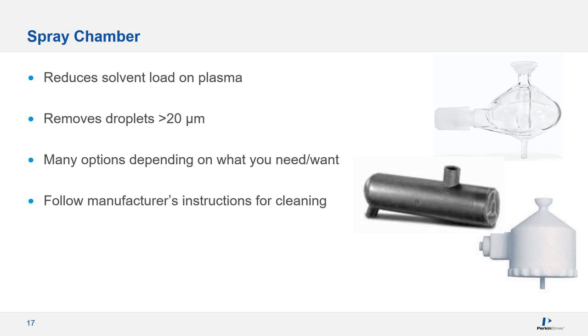Be aware that some spray chambers have a specialized coating on the interior surface, and the manufacturer's instructions should always be followed for any cleaning to avoid damaging that.